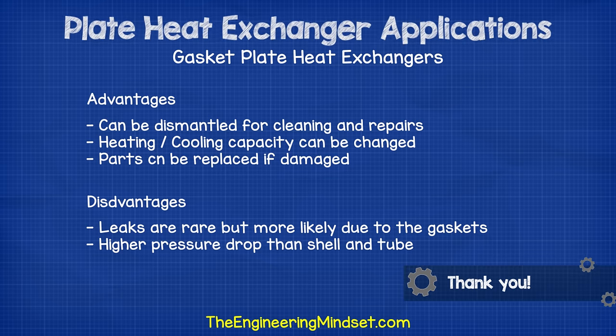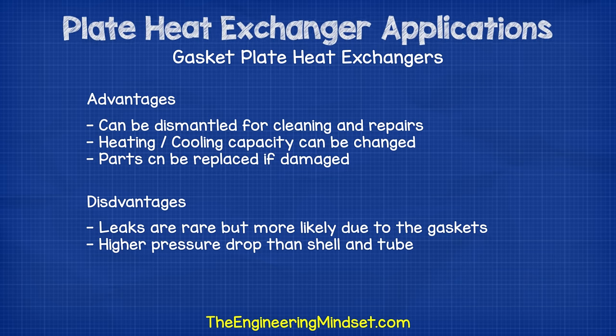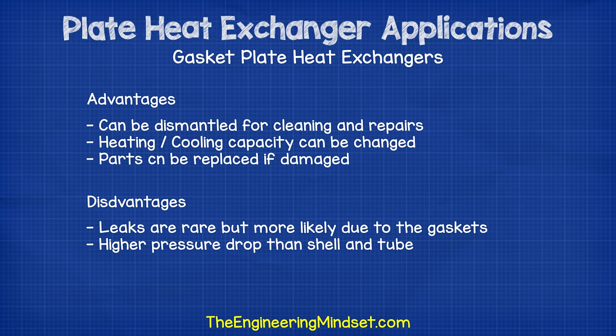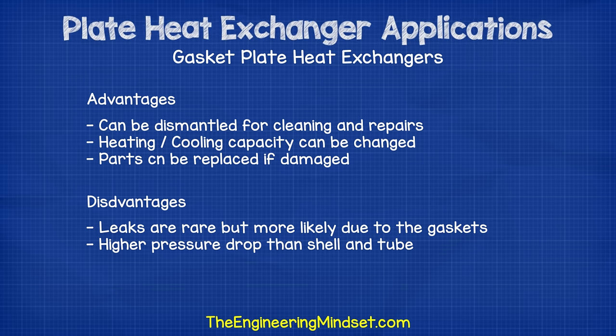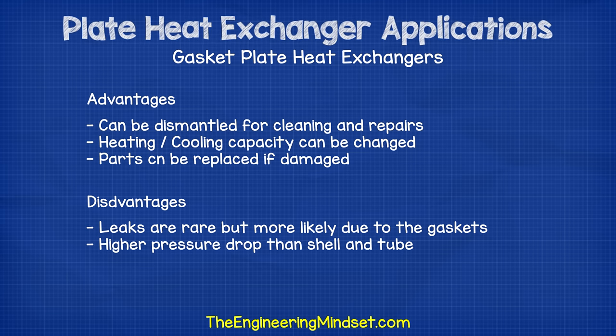Considering the pros and cons of gasket type: the pros are that it can be dismantled for cleaning, the heating and cooling capacity can be changed, and parts can quickly be replaced if the unit is damaged. The cons are that leaks, while rare, are more likely due to the gaskets, and this unit will have a higher pressure drop than a shell and tube heat exchanger.